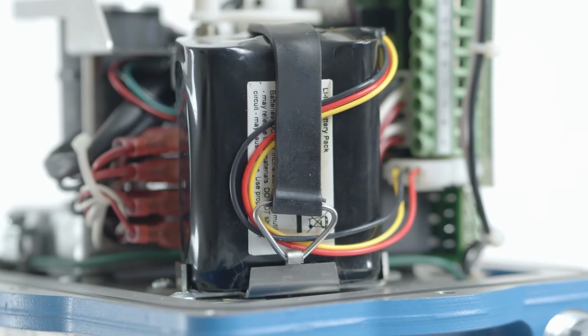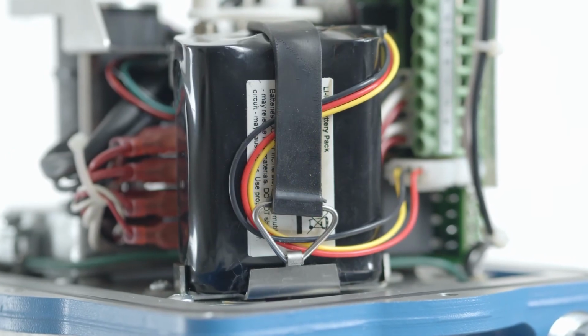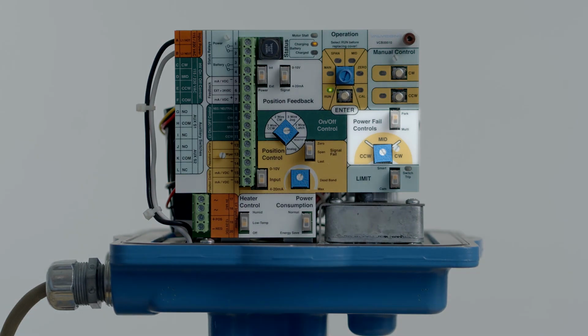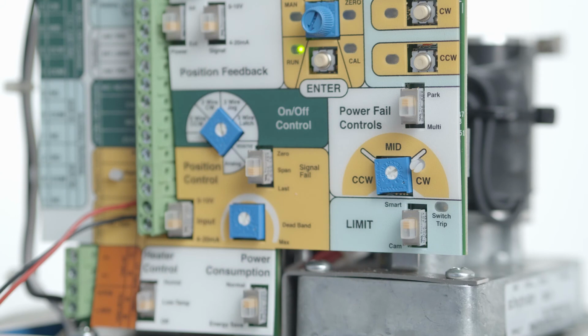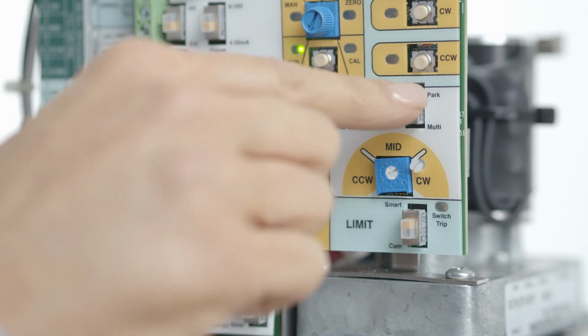If the actuator includes the optional battery backup, there are a few more selections to make. The actuator can be configured to park, meaning it will drive to the fail position immediately upon loss of external power. Or we can select multi, whereby the unit will continue to respond to a control signal if still present using battery power. The default configuration is park. Selector switch is up. To select multi, move the switch down.